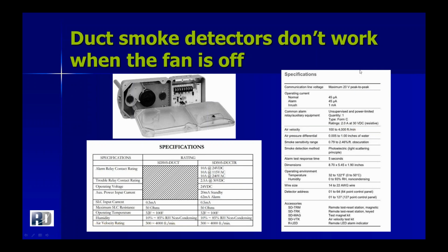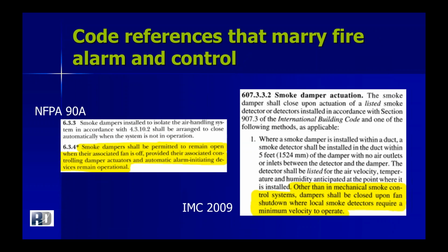The low end is not 0. So when an air handling unit is off, the velocity would be 0 for all practical purposes. Hence, the duct smoke detector becomes non-operational, non-functional when the air handling unit is off. So now these two code references play a much bigger role, still with NFPA 90A, as we've highlighted there, but I think it's better illustrated in the IMC under subparagraph 1, where it indicates other than mechanical smoke control systems, dampers shall close upon fan shutdown where local smoke detection requires a minimum velocity to operate. So what we're looking at here is really the marriage between fire alarm and controls.